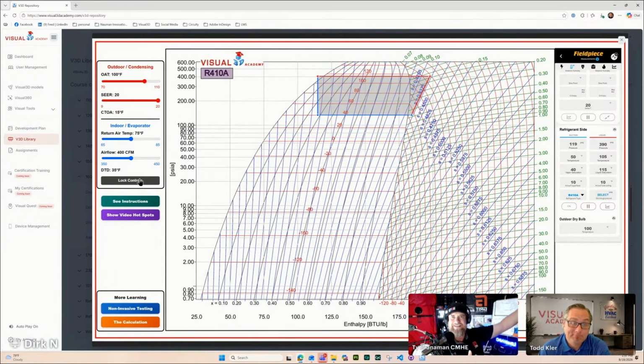They've got a why problem. Why is it so high? Like, what's going on? And there's a lot of things that can cause that. And we can go over the whole diagnosis, but the first thing is like, hey, that's not normal. We need to see what's going on. So the age of the equipment, luckily there's not a lot of the 80s systems out there, which I still like. I have a jug of R22. I still work on some of those that are out there. It's just understanding, hey, what was normal back then is a lot different than what's normal now.